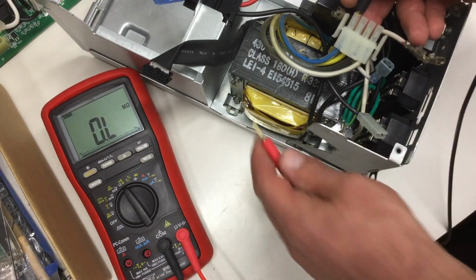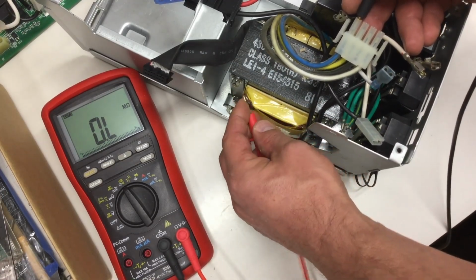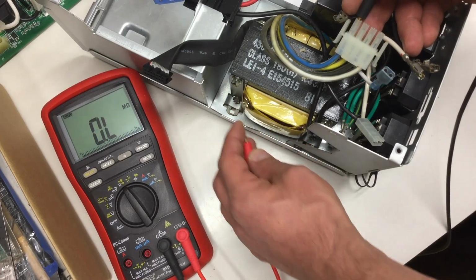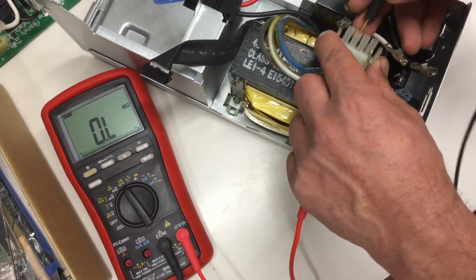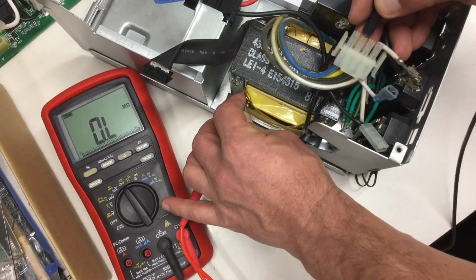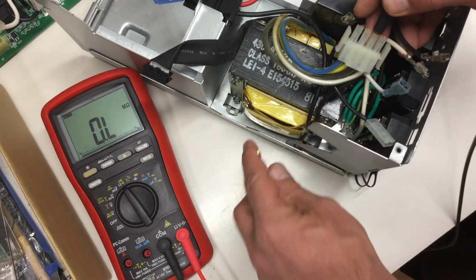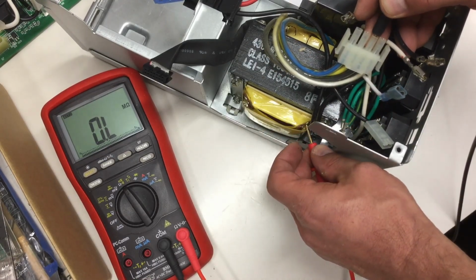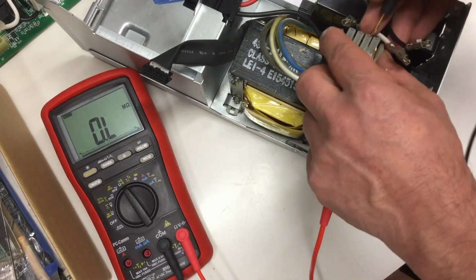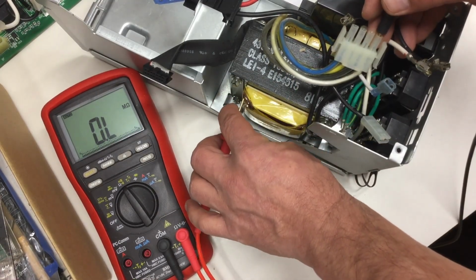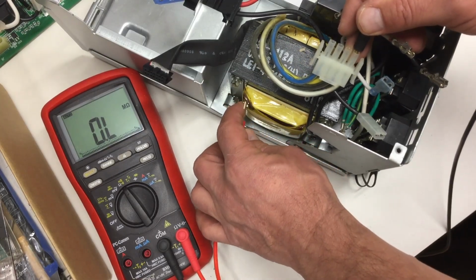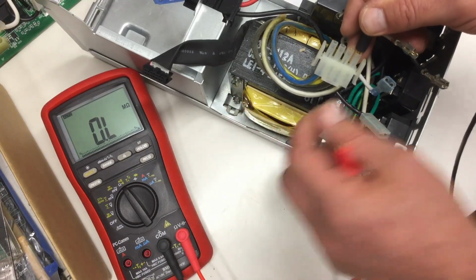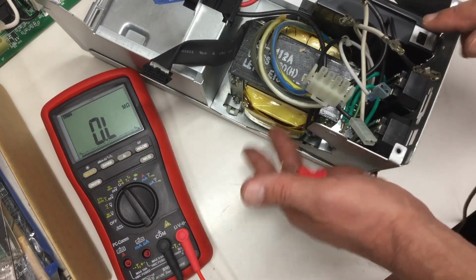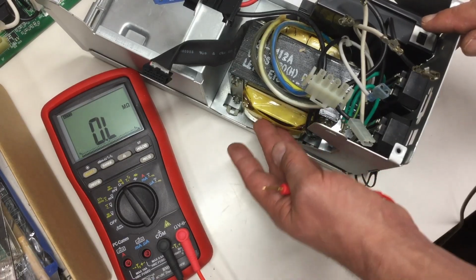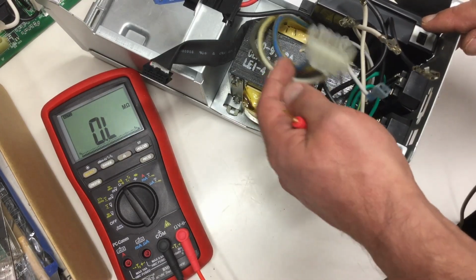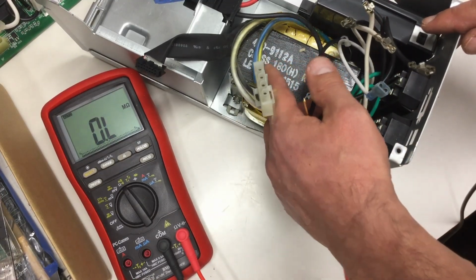Just to check if there's any connection to the high volt side. Nope. Nope. Nope. Don't have to switch that. Nope. So at least we know that the low voltage side, which is driven by the battery in case of a total power failure, is isolated from the mains side.